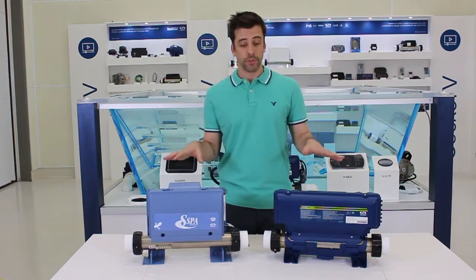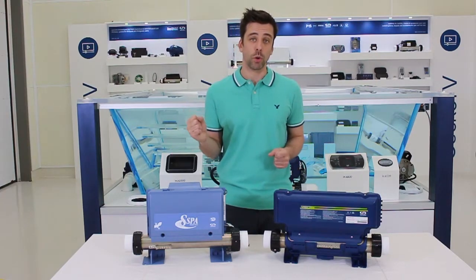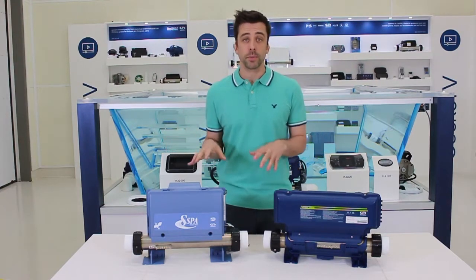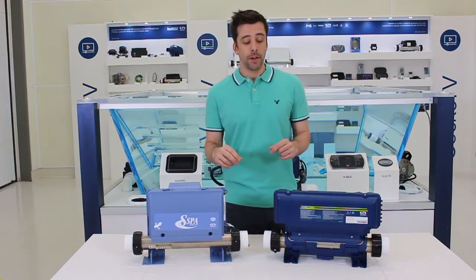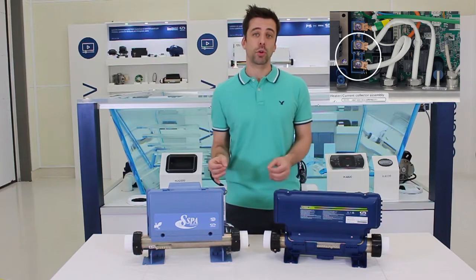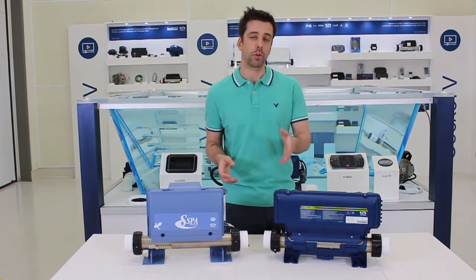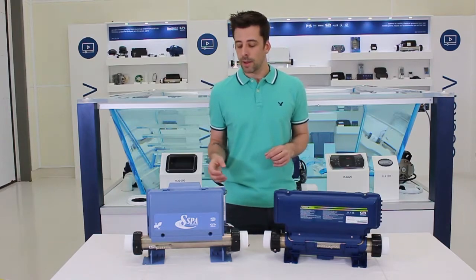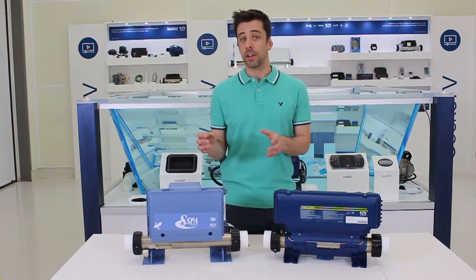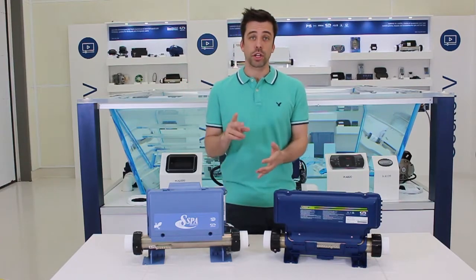However, if the whole system was operational and it started to trip and it won't hold anymore, very likely something shorted out. So first thing I will recommend: unhook both heater leads from the board. The most common source of GFCI tripping by an accessory is the heater that is shorted out, or the element more likely. So try that, and if it holds, change the element or change the heater.